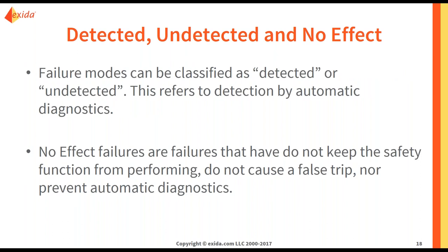Let's define detected, undetected, and no effect. Failure modes can be classified as detected or undetected, and in this case we are referring to detection by automatic diagnostics. You might also have no effect failures, which we went over. These are failures that do not keep your safety function from performing, do not cause a false trip, and are not preventing automatic diagnostics from monitoring your signal. Therefore, they are no effect failures. They might be a little less accurate, however they are not keeping you from responding to a hazardous event.